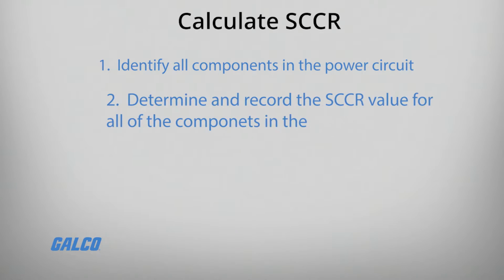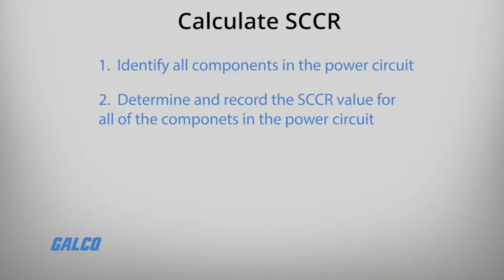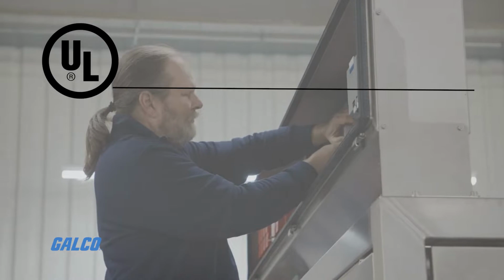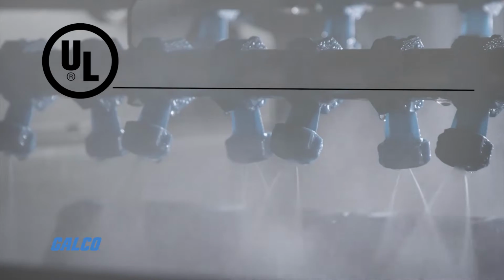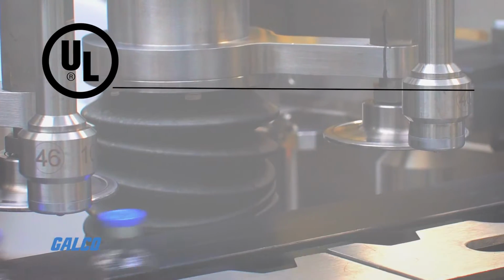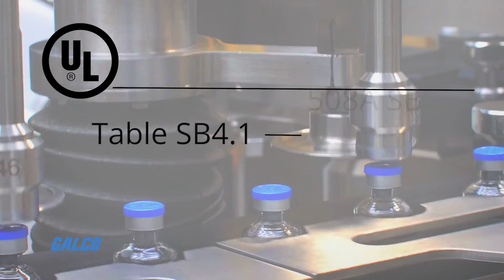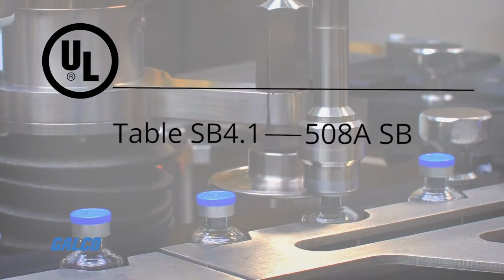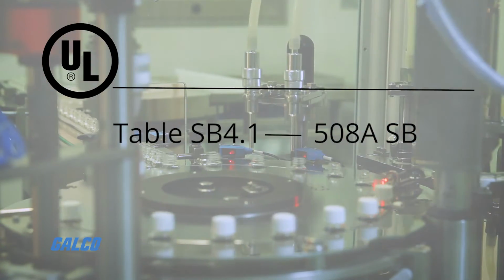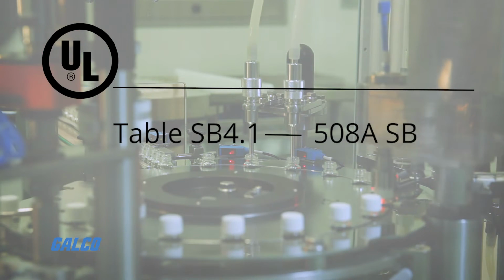Next, determine and record the SCCR value for all of the components in your power circuit. Again, these are typically marked on the components. If not, reference UL Table SB4.1, published under UL Standard 508A.